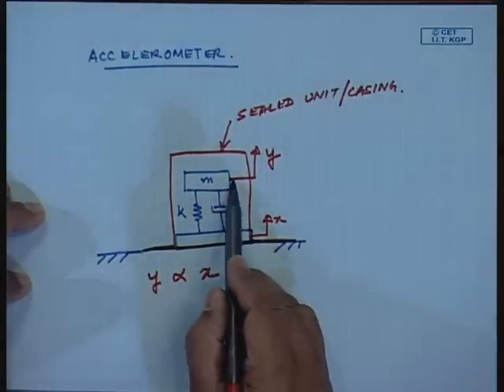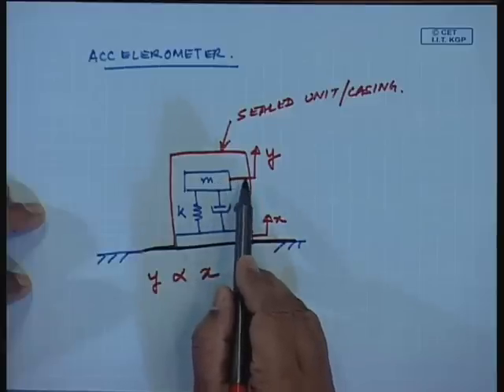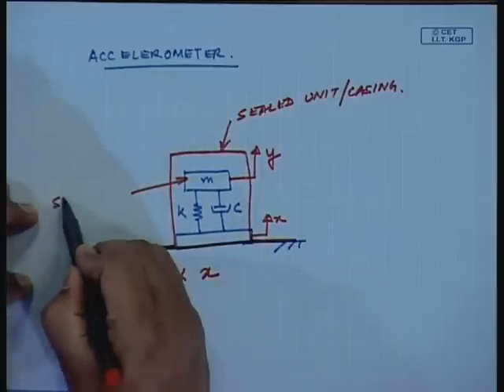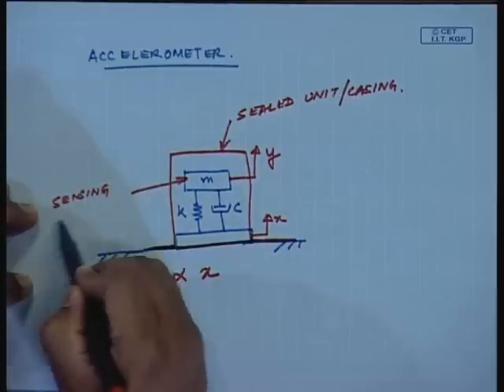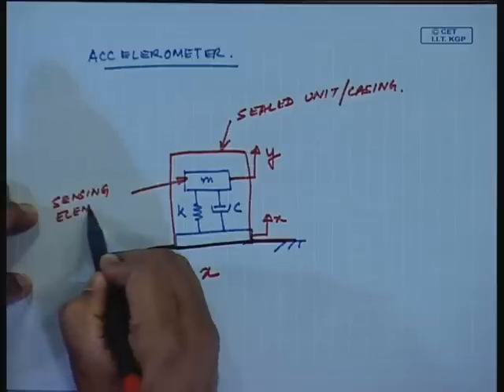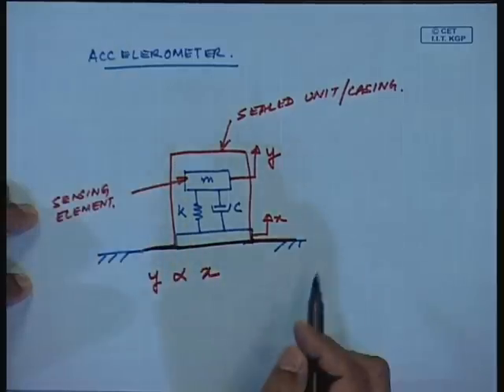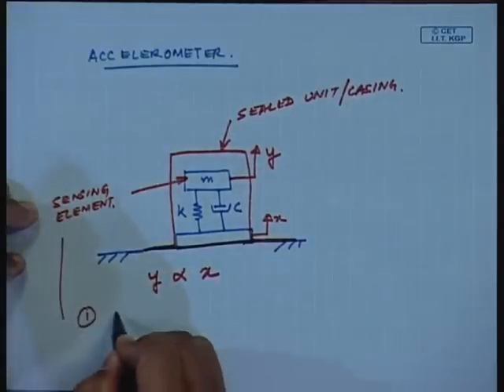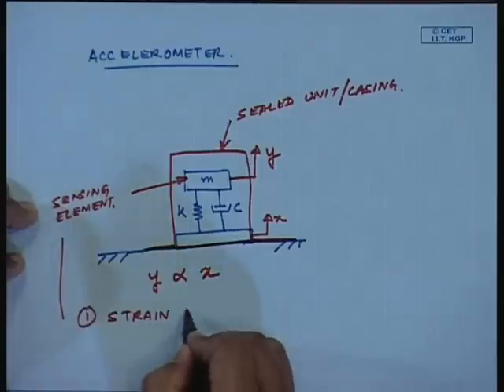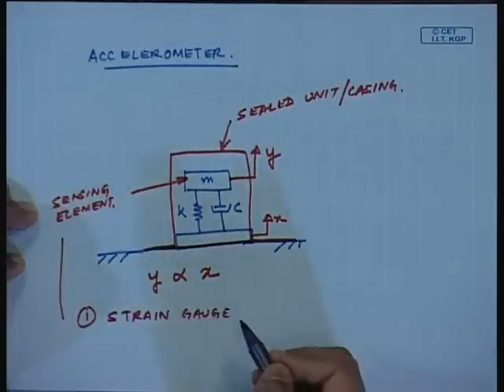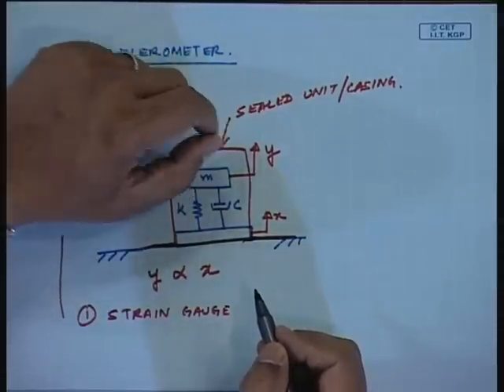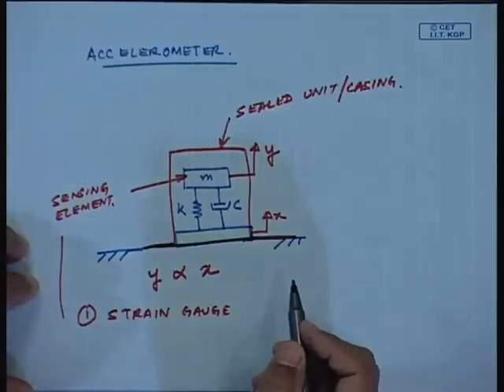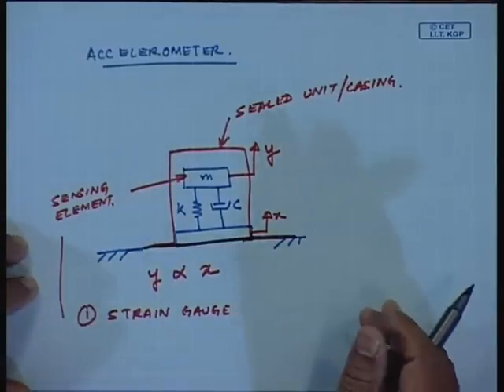Because this mass is having a motion y, I could be putting certain sensing elements. The sensing element could be strain gauges - because of this motion there will be some strain, and this strain will be indirectly responsible for giving a measure of x. This is what initially was the strain gauge type of accelerometer. But strain gauges need a certain power supply, they need a resistance which should not change with temperature. So there are certain problems with this kind of accelerometer.